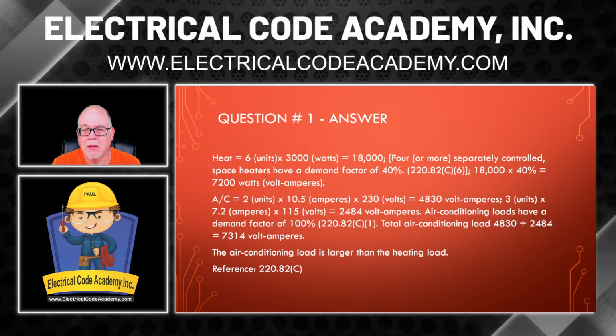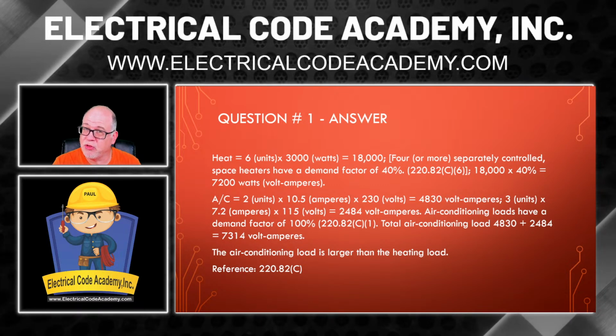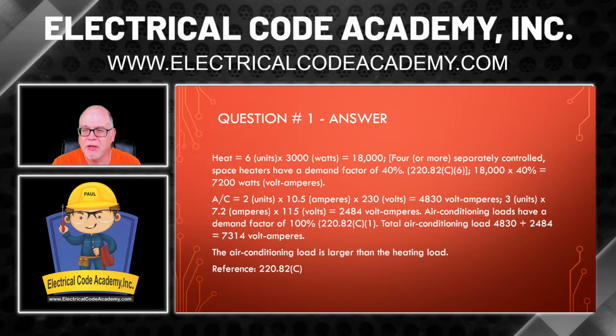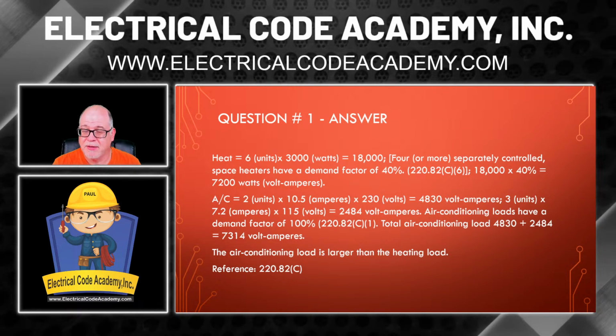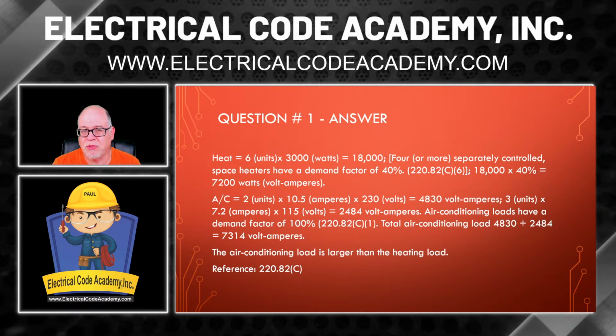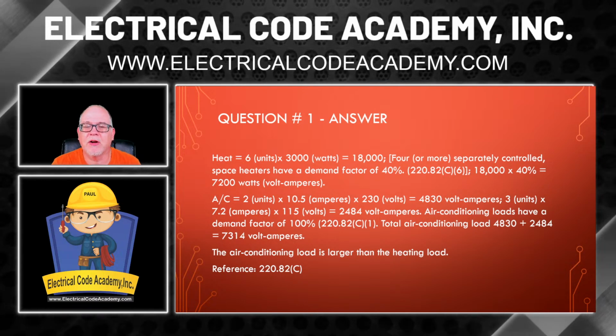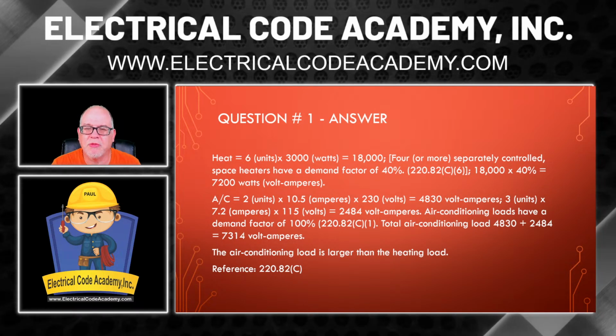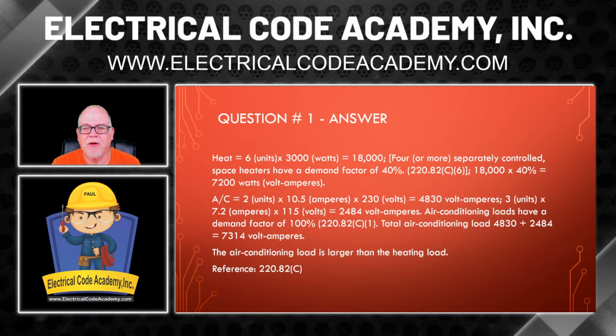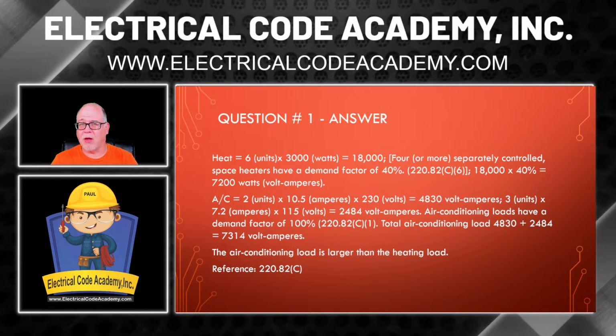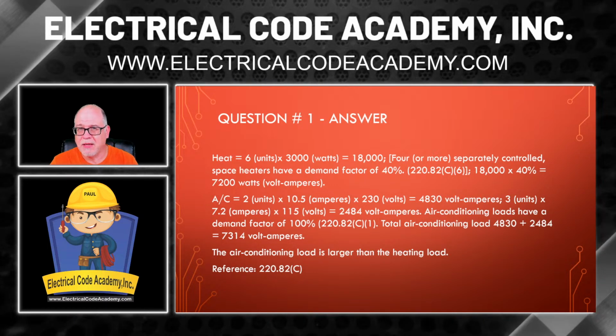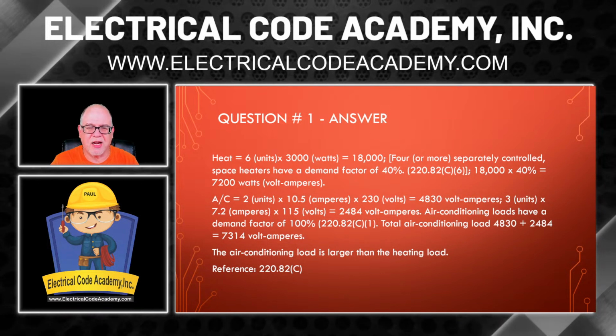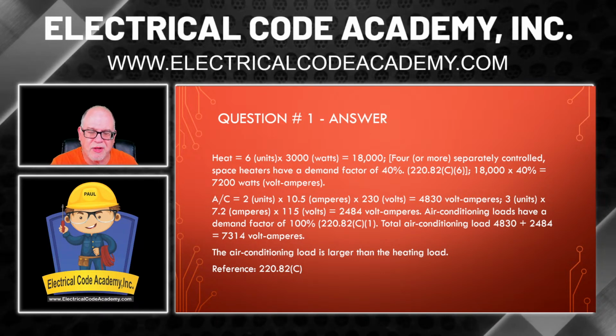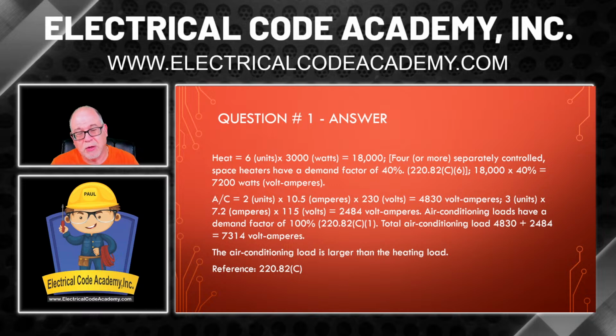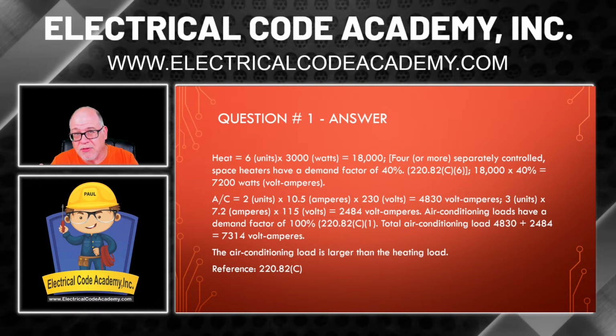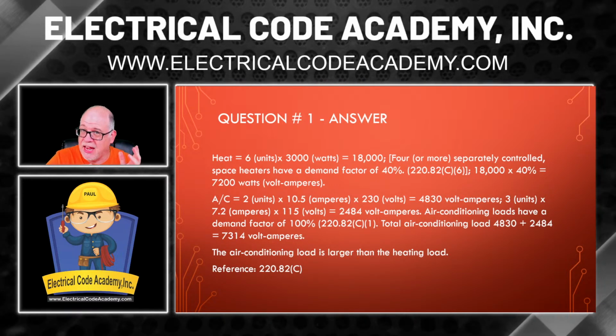Okay? Now let's do the 3 7.2-amp air conditioning units. That would be 3 times 7.2 times 115 volts. That is 2,484 volt-amperes. Remember Ohm's law: in order to find VA, it's synonymous. We're just going amps times volts equals watts, and watts is synonymous with VA.